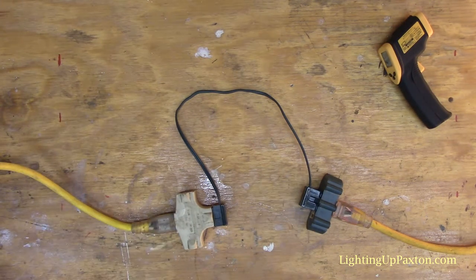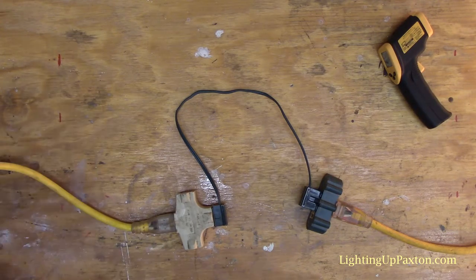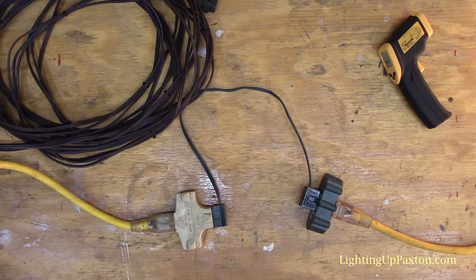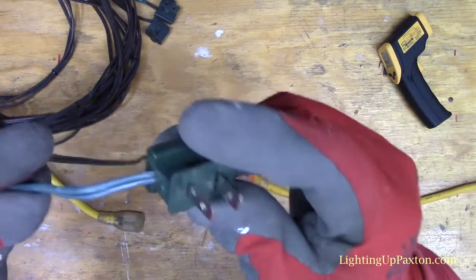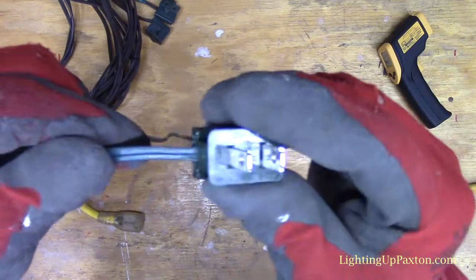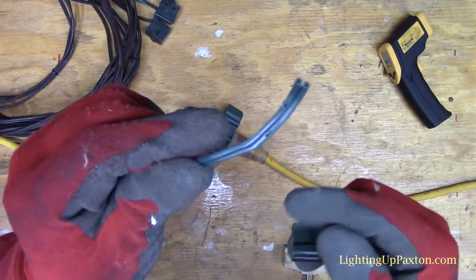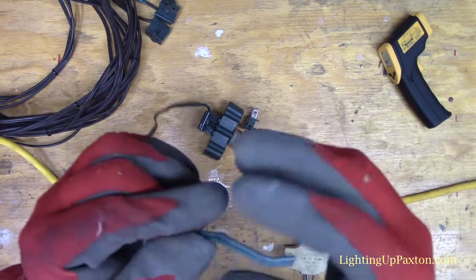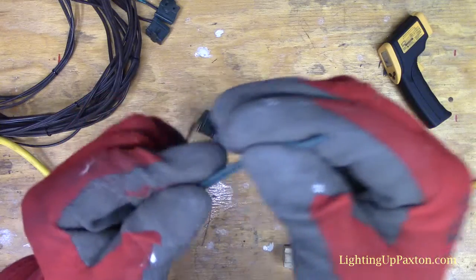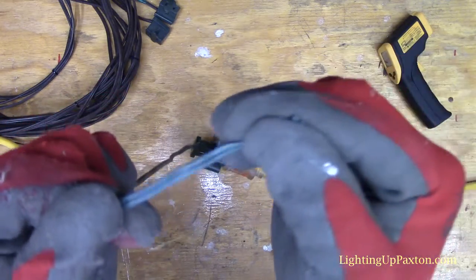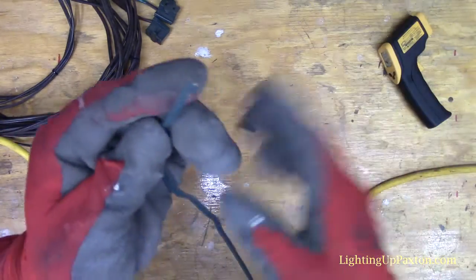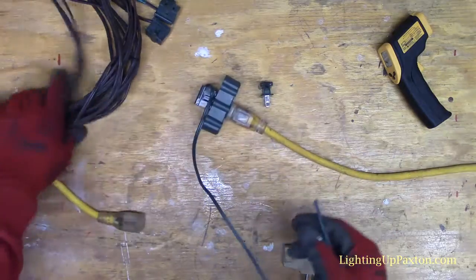Let's unplug everything. Here's what I've got - we got a long coil and we're going to plug this thing in next and see if this will do it. Oh yeah, here we go. This is how hot it was - look at it just pull right out of the plug. Talk about an angry piece of wire. I mean that's like play-doh. I'd say we're definitely on the verge of something bad there.